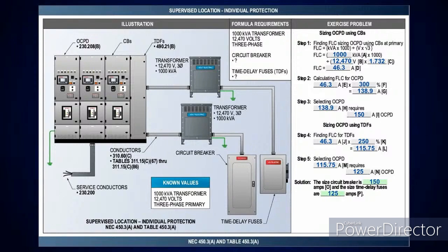It's 1,000 kVA and a 12,470 volt three-phase primary. Now, as I look at that, you'll notice I don't have an impedance there. So when you're looking at that table, you're going to see where it says any. When you come across there, you're looking at primary protection, and of course this is over 1,000 volts. If I'm sizing the circuit breaker, it's going to tell me to take it at 300%, and if I'm sizing the fuse rating, it says take it at 250%.